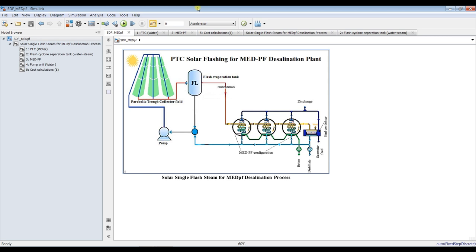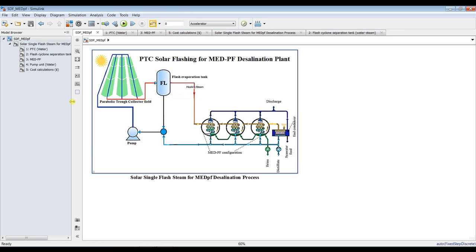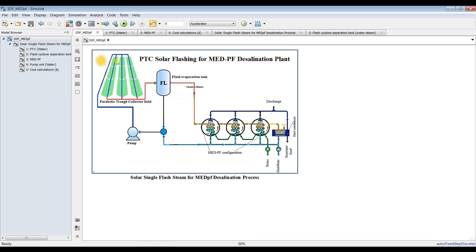We are going to drive thermal power for such a field by the use of a parabolic solar field, with water-steam inside, attached to a flash evaporation tank or flash cyclone tank. There is no steam to be generated from the solar field — this is a liquid loop. Hot water is going to be flashed in a flash evaporation tank in order to generate steam.